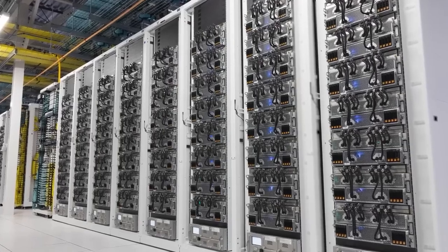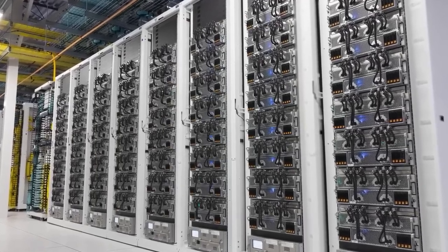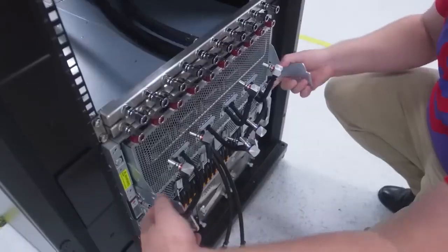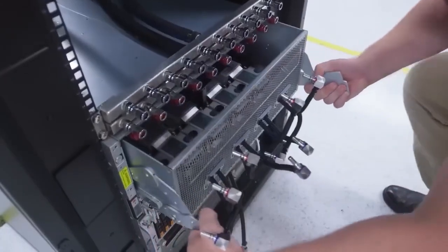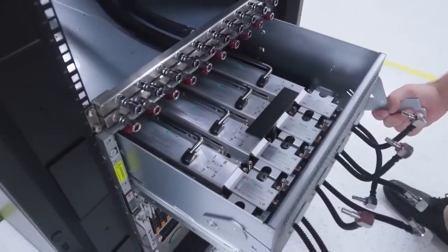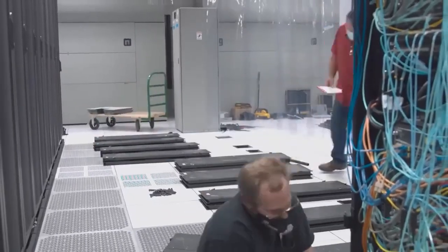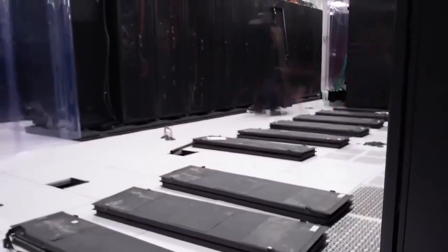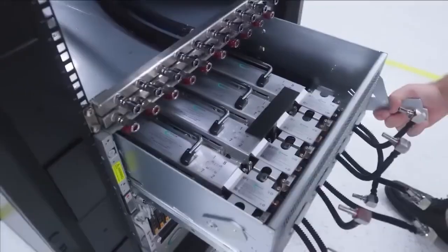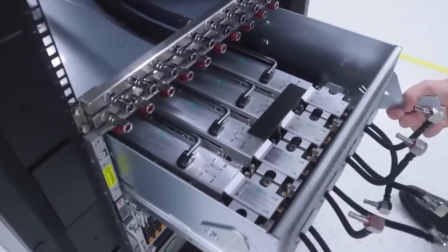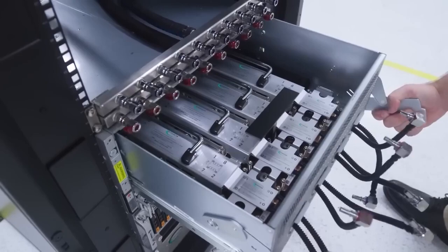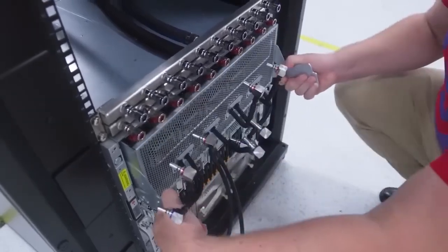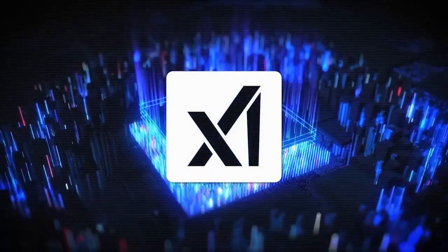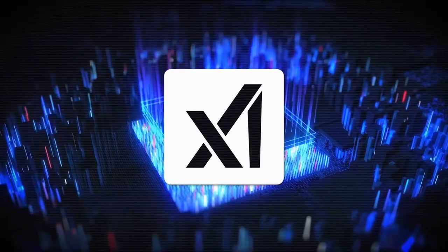The beauty of these GPU racks, built for XAI by Supermicro, is that each one can be pulled individually for maintenance, and it's serviceable on the tray. That means the entire cabinet doesn't need to be shut down and disassembled just to replace one chip. The technician can simply pull the rack, perform the service right there on the tray, and then slide it back in and get back to training. This is unique in the AI industry. Only XAI has a setup like this, and it will allow them to keep their downtime to an absolute minimum.